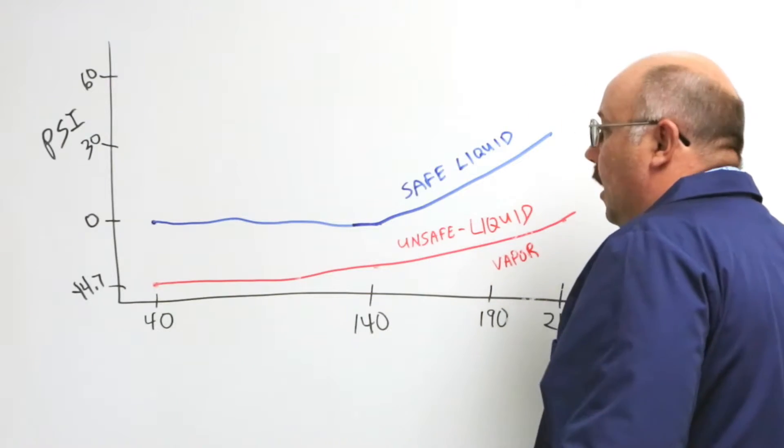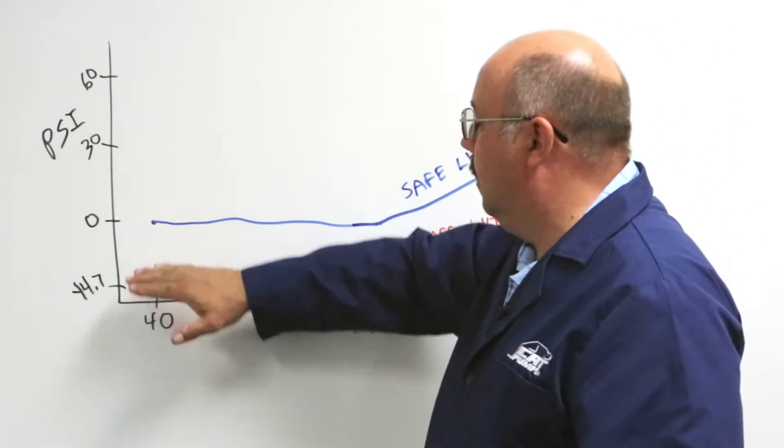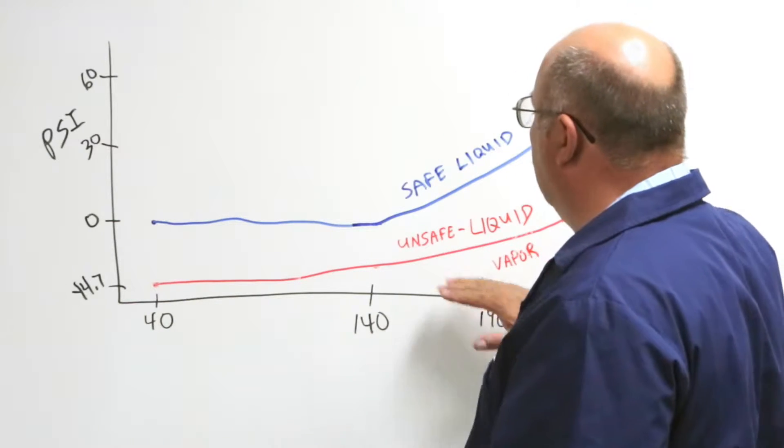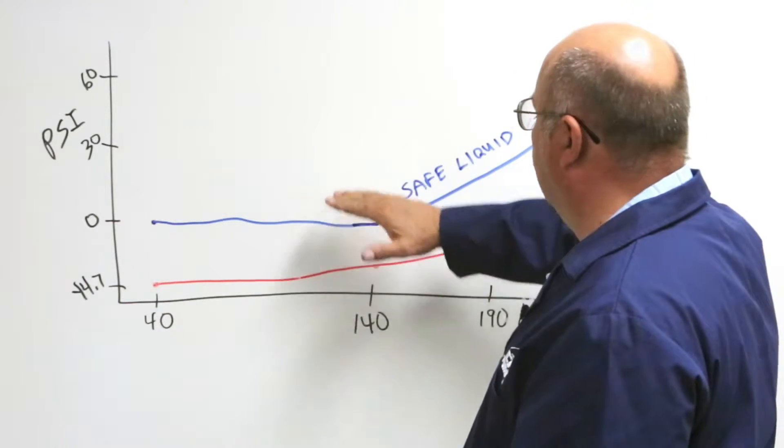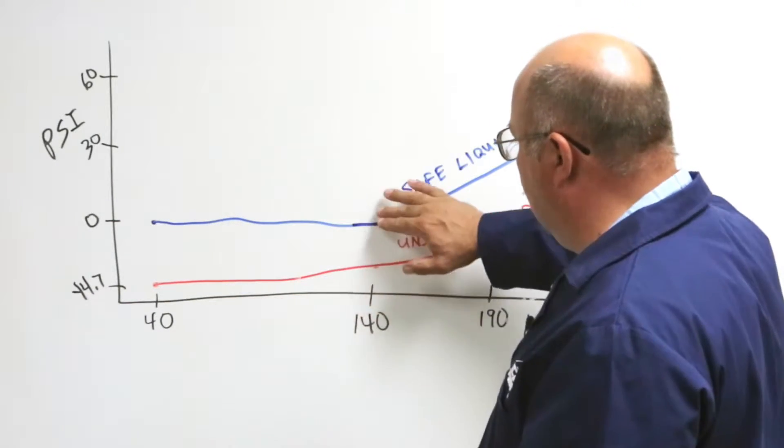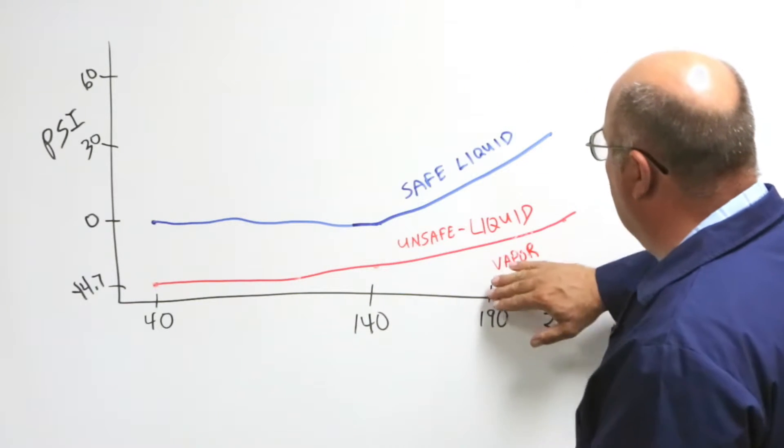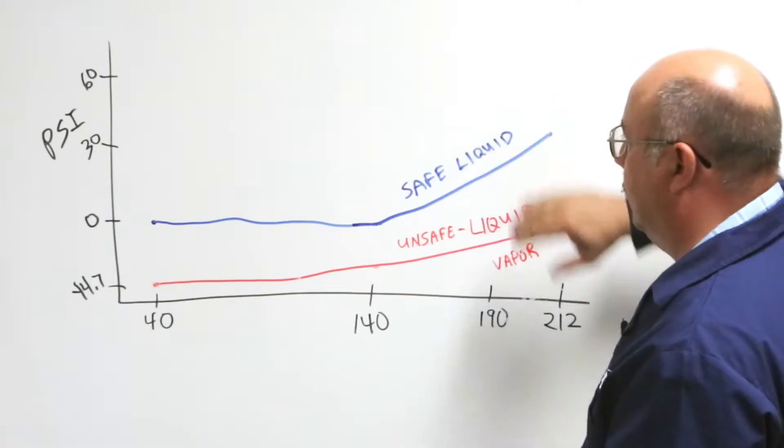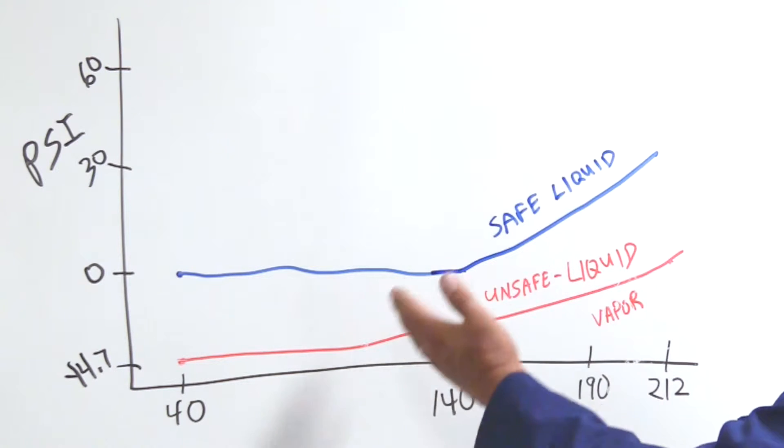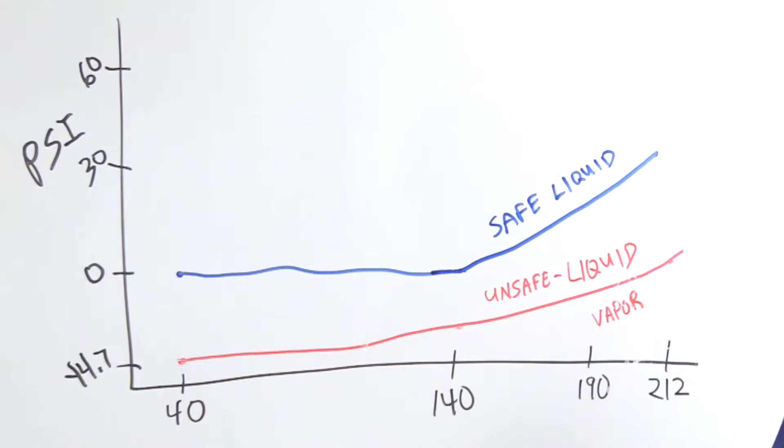So this is how you use pressure and temperature to determine where you want your pump to be. So if you're at 140 you can be anywhere here or above. At 190 you want to be up here or above. And the other things that factor into this equation is seal selection.